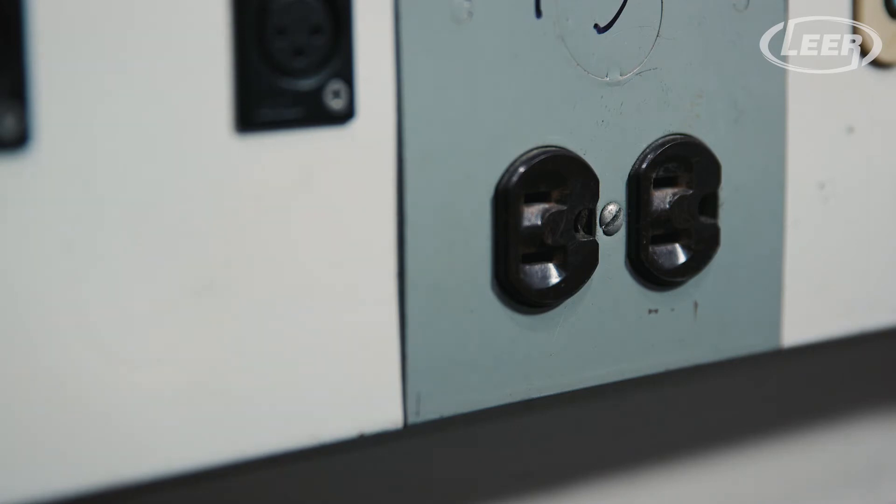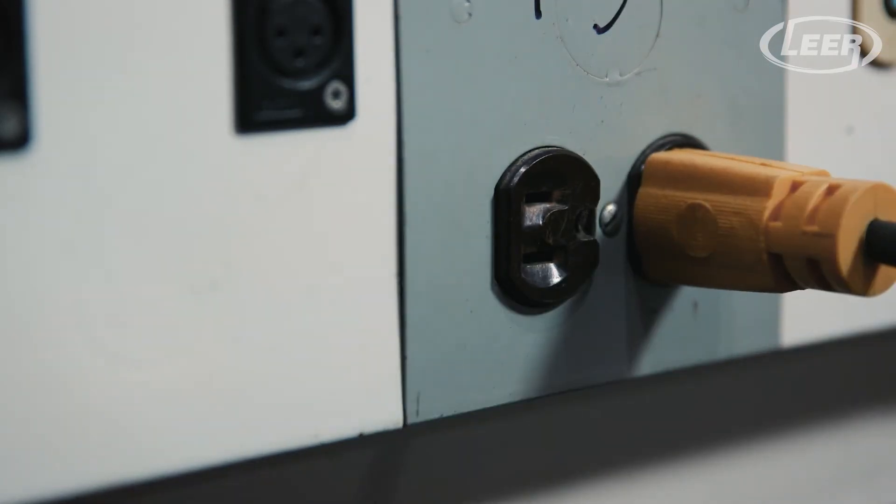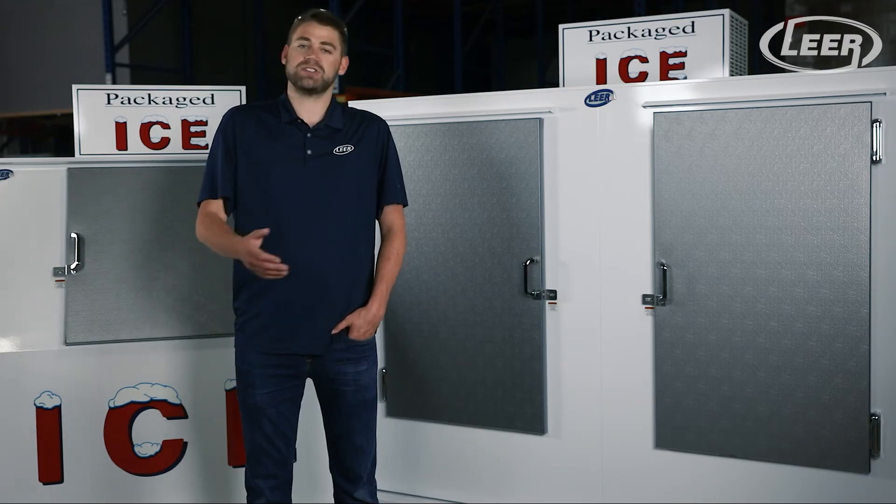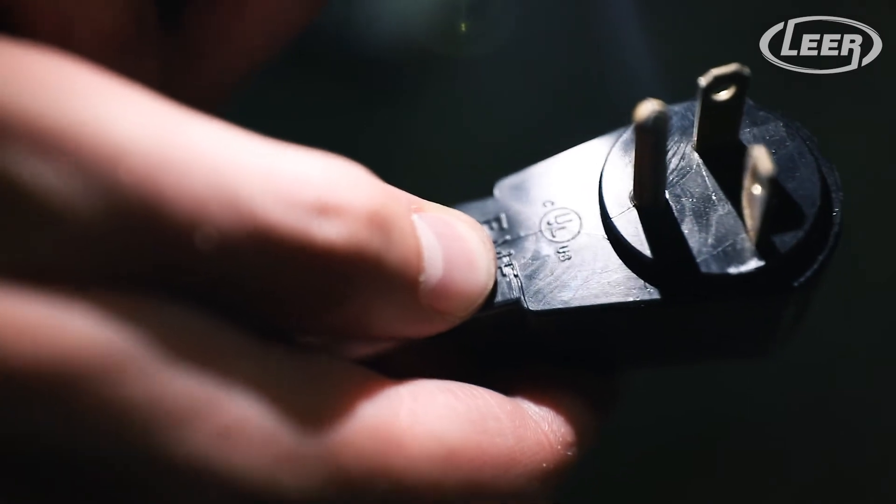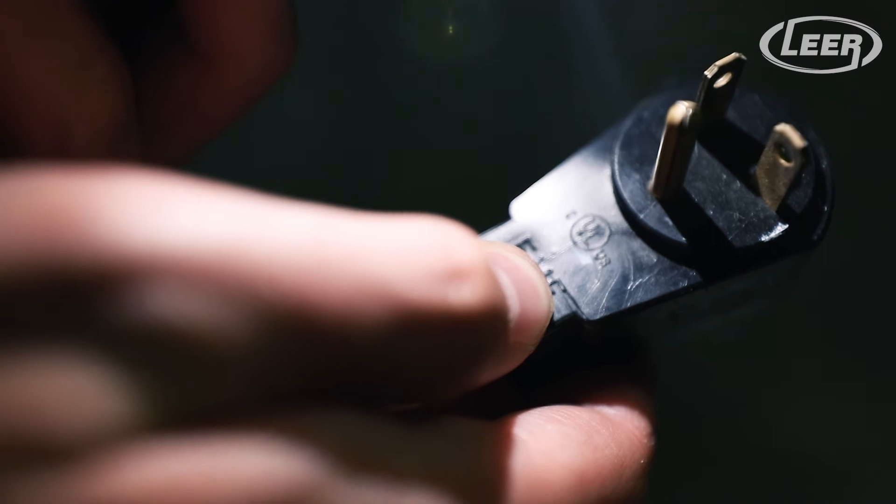The merchandiser requires a 115-volt single-phase outlet. The amp draw ranges between 6 and 13 depending on size and cold wall versus auto defrost. UL certification requires all models larger than the model 100 to use a 20-amp plug.